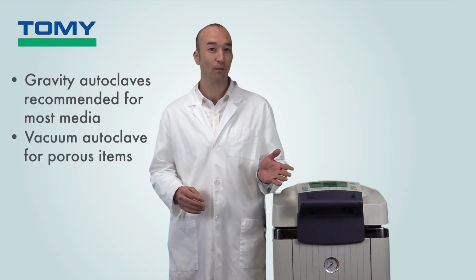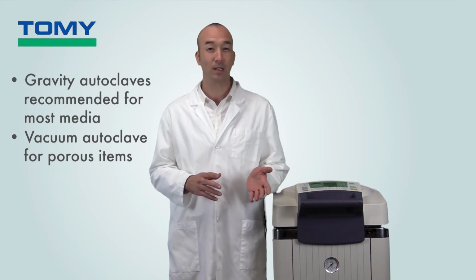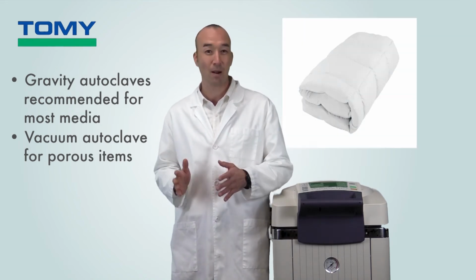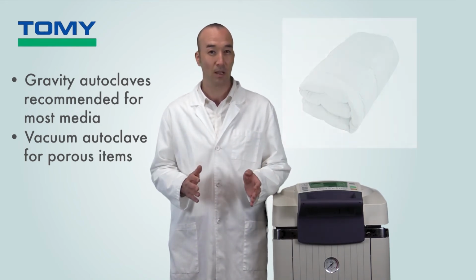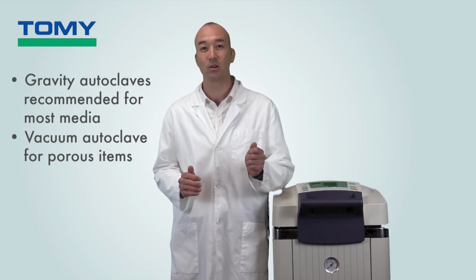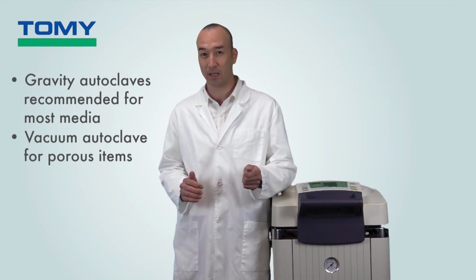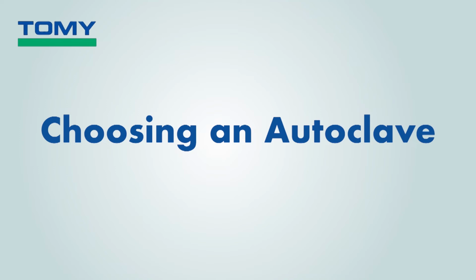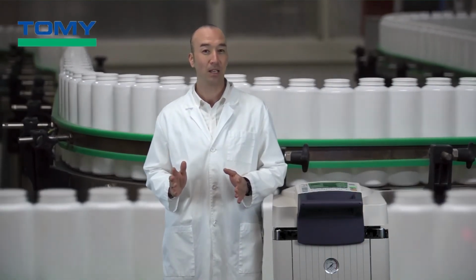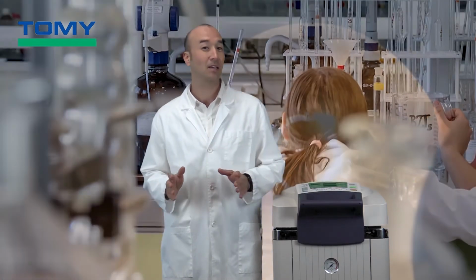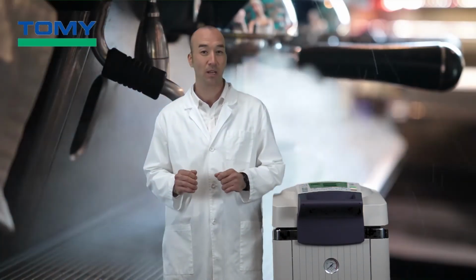On the other hand, if you're autoclaving items that are porous or contain hard to reach areas, such as fabrics or wrapped surgical kits, you'll need a vacuum mechanism to make sure that the steam penetrates your media completely. Though you may now know what type of autoclave is suitable for your needs, you'll also need to assess your throughput capacity, available lab space, and access to electricity, water, and house steam.